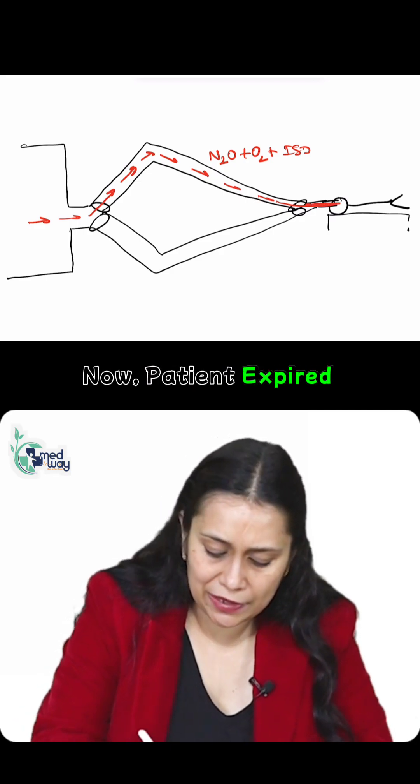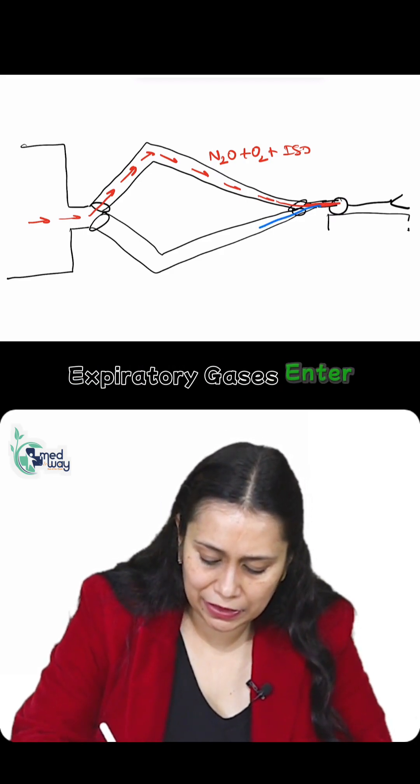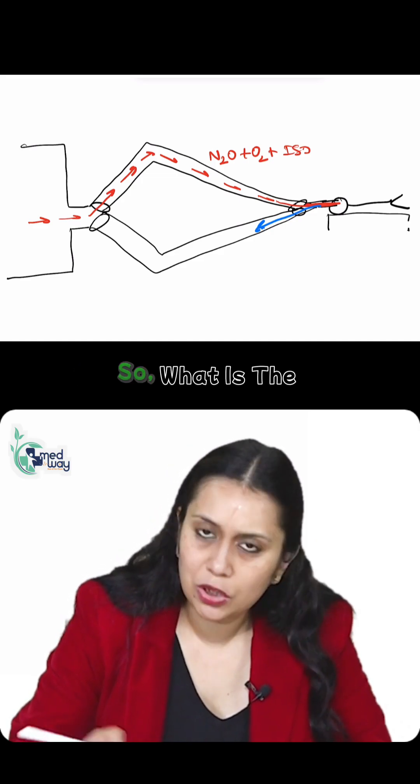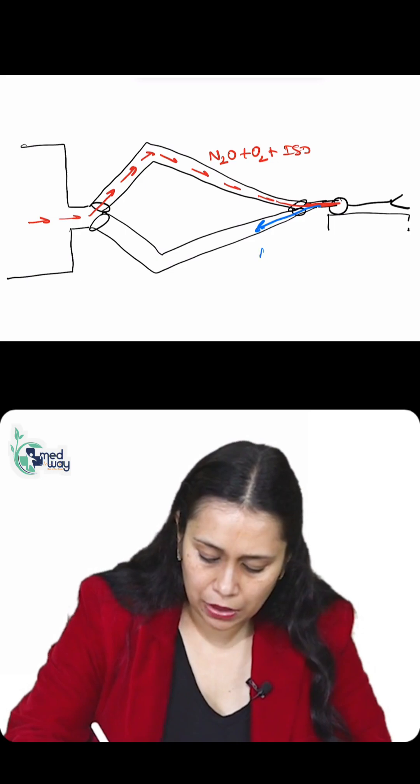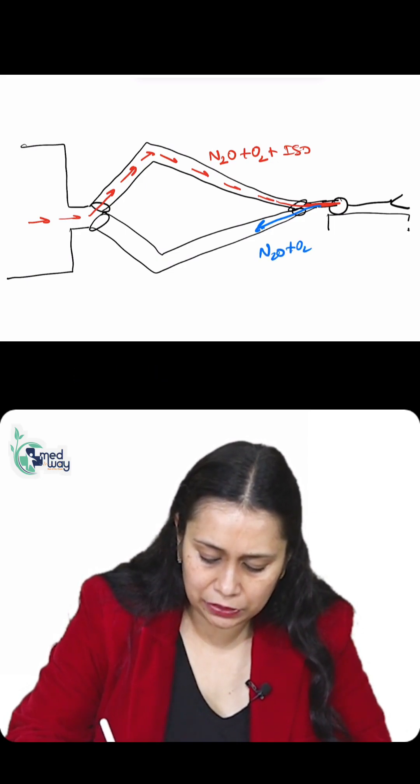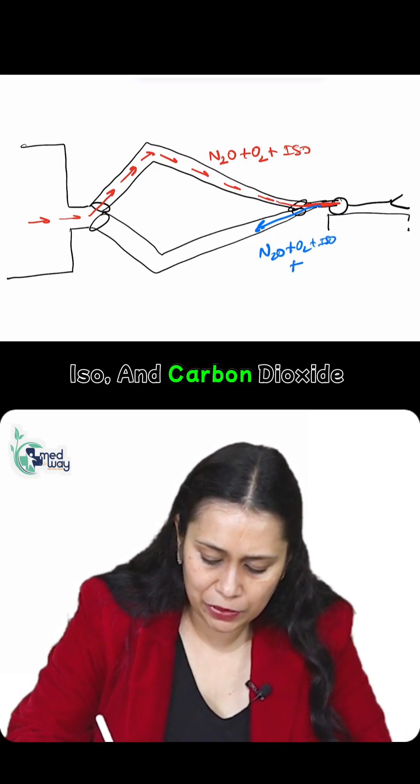Now, the patient expires. Expiratory gases enter the expiratory limb through this one-way valve. What are the expiratory gases? Nitrous oxide, oxygen, iso, and carbon dioxide.